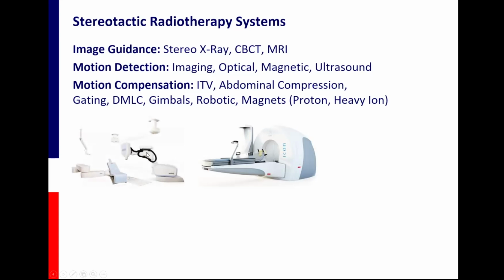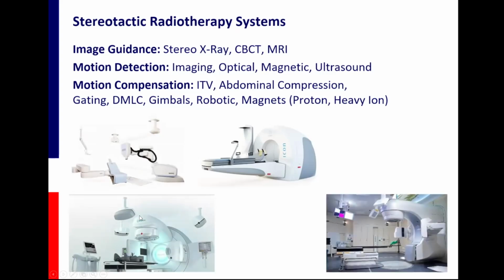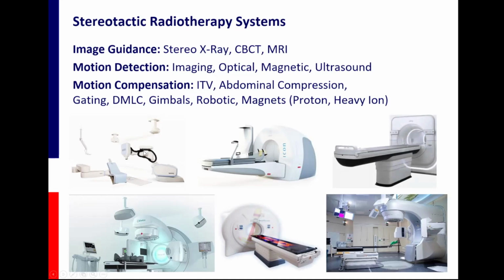The CyberKnife, which we have in Kiel and Frankfurt, uses stereoscopic X-ray images to register to the treatment planning CT, and then steers the robot according to that position. Or here, modern linear accelerators from Elekta and Varian, for example, with cone beam CT, X-ray images, ultrasound information, and a surface scanner. So basically, all these systems have highly dedicated image guidance systems available to locate and treat tumors very precisely. Tomotherapy, for example, with integrated CT information, can now also gate the beam with the Synchrony system that is normally used on a CyberKnife for tracking, or there is an MR-Linac system, where you have MRI during treatment and see the tumor all the time, which is really great.